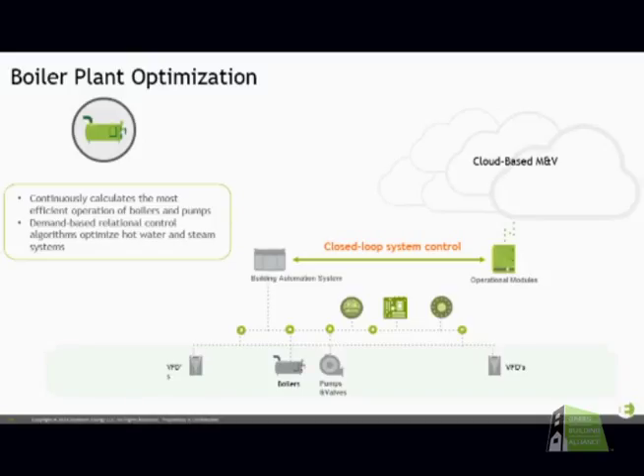Just quickly on that, the reality is for a lot of facilities that just have packaged rooftop units, a lot of these components are all in one box. That's really what a rooftop unit is, so the cooling towers aren't separated from the condenser water pumps and the chiller, it's all in one big box. When you have that, there's a limit to how much you can do and a limit to the efficiency you can have. Like the scale I brought up before, most new plants are around 0.7 kW per ton, most rooftop units are around 1.1 kW per ton, so they're a lot less efficient, just by their nature.